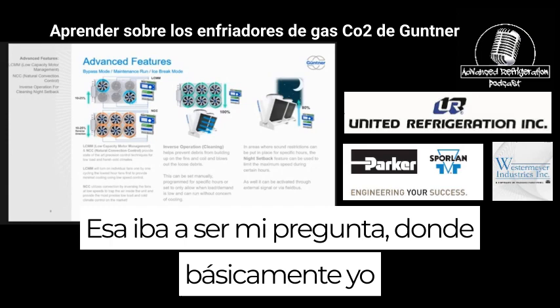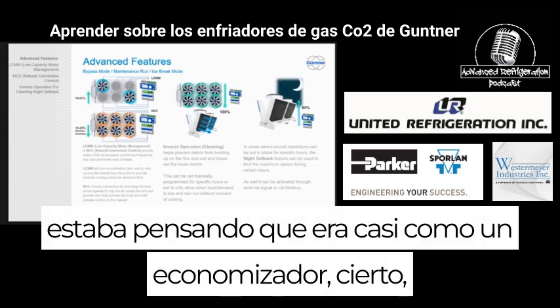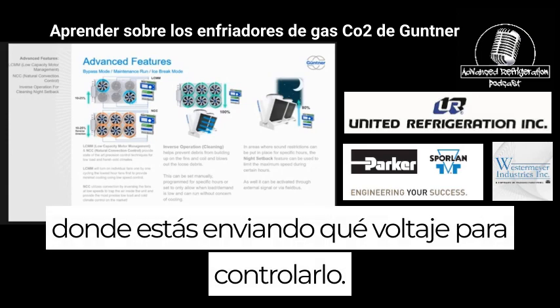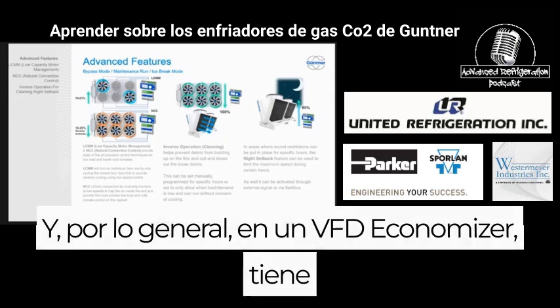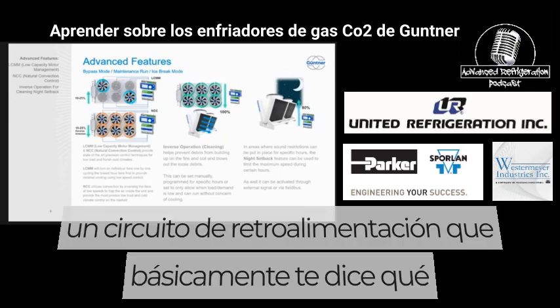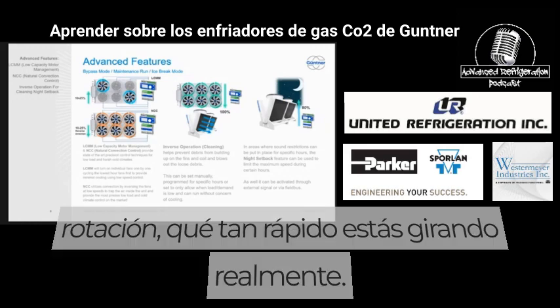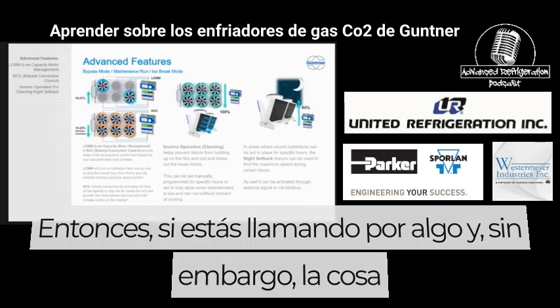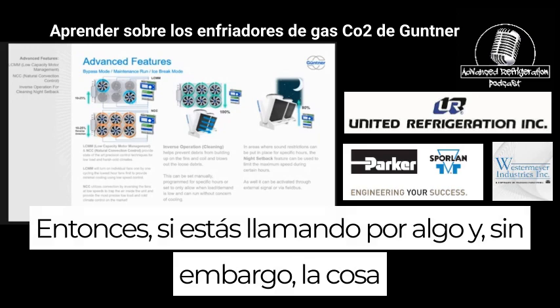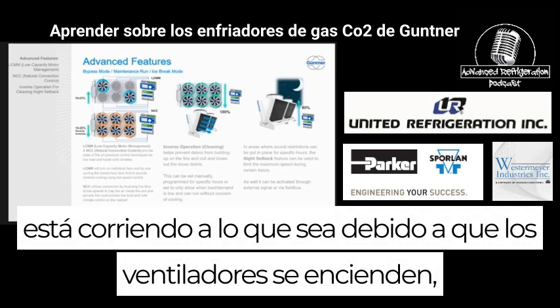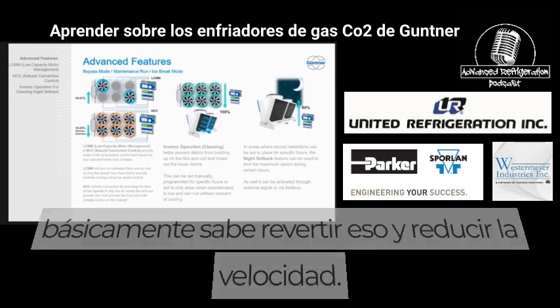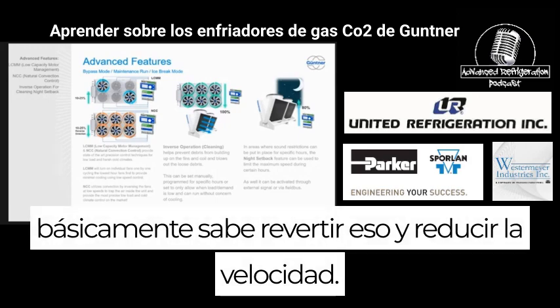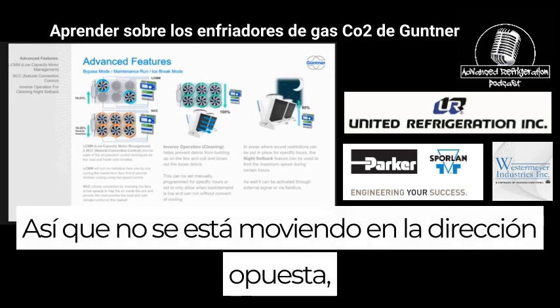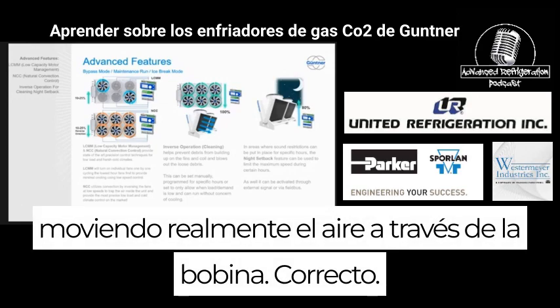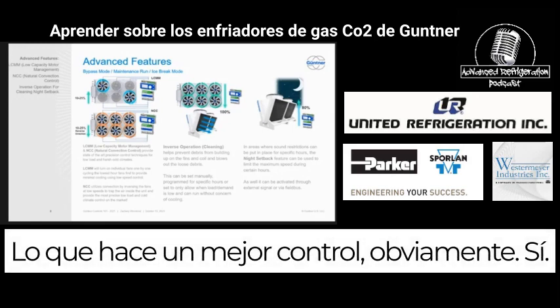That was going to be my question, where basically I was thinking that it was almost like an economizer, right? Where you're sending out what voltage to control it. And typically on an economizer, VFDs, you have a feedback loop that basically tells you how fast you're actually spinning. So if you're not calling for anything and yet the thing is running because of the fans coming on, it knows to revert that and slow it down, so it's not moving in the opposite direction, actually moving air across the coil, correct? Which makes for better control, obviously. Yeah.